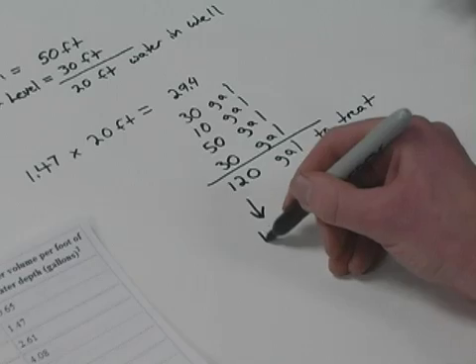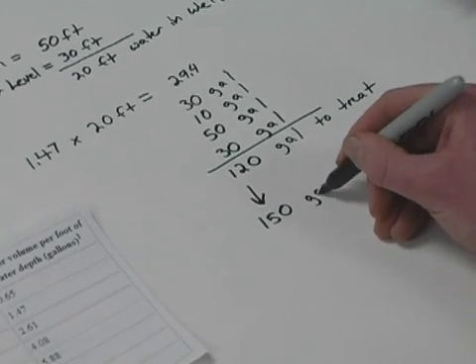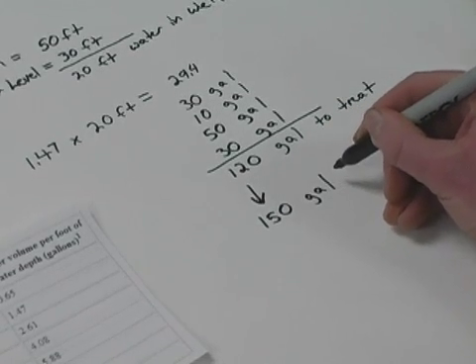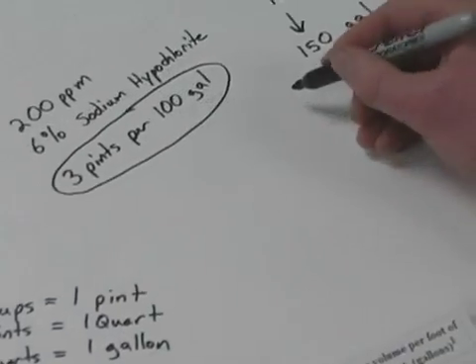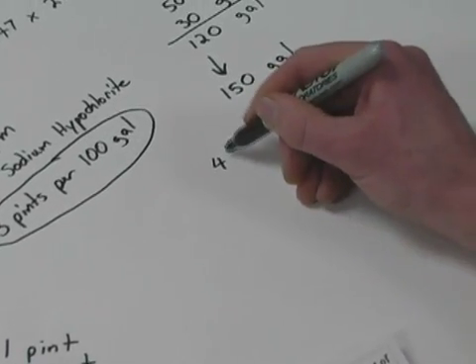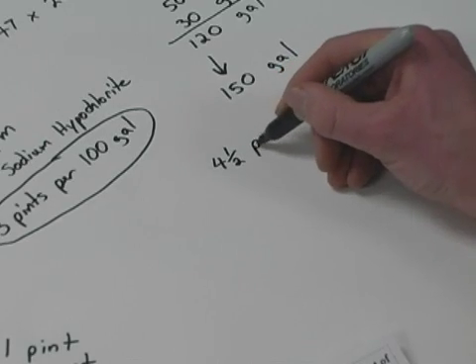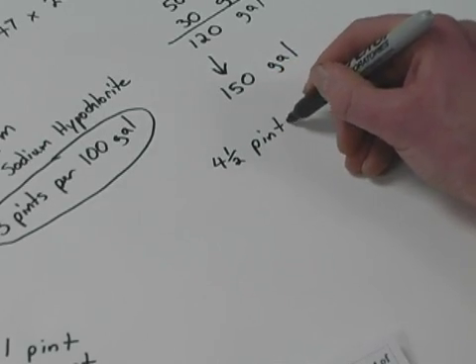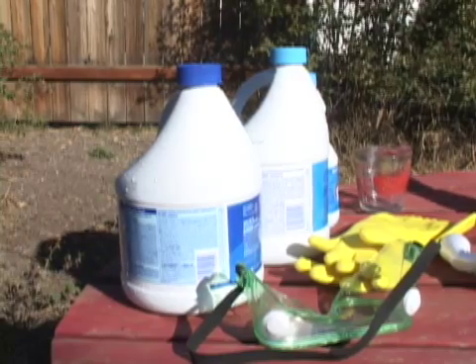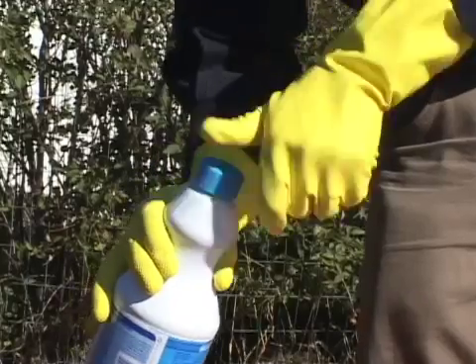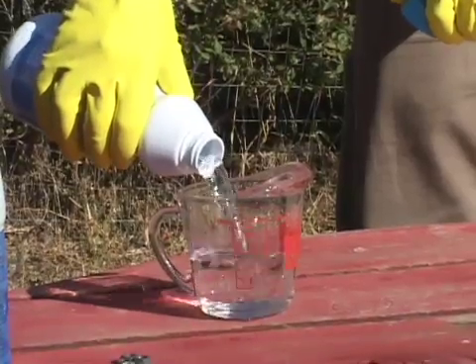We will round our gallons to be treated up to the nearest 50 gallons, which gives us 150 gallons. At 3 pints per 100 gallons for 150 gallons, we need to add 4.5 pints of liquid laundry bleach. There are 2 cups in a pint and 2 pints in a quart. You can use a standard household measuring cup to measure off the amount you calculate.